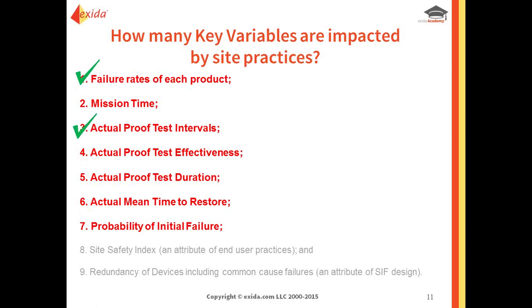We do know that the proof test intervals will change if they don't do things correctly. The effectiveness obviously is going to change. The duration is going to probably stay the same because that's actually set - we want to do this test at this amount of length. Mission time is always going to be here, so there's no real variance there. However, the mean time to restore will change - let's say the engineer can't figure out how to operate something in a need of emergency - and the initial failure, of course, will also change.